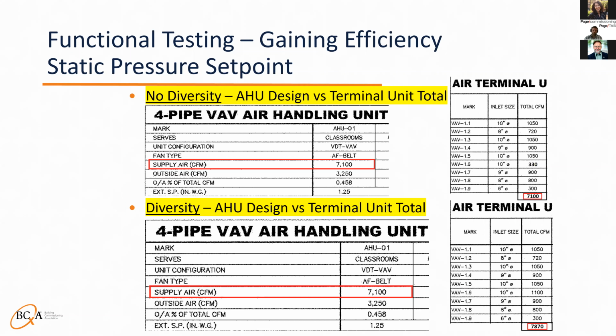Now look for the worst case damper, meaning the terminal unit's damper that is the most open. This damper should be no more than 90% open and no less than 80% open. If you see any dampers that are 100% open, there is an issue with the static pressure set point and it may need to be higher. If you see all dampers below 80% open, there is an issue and the static pressure may need to be lower.